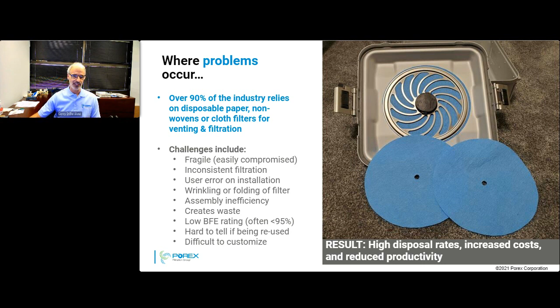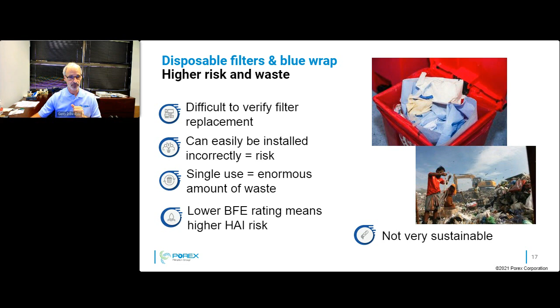Okay, so disposing of filters and blue wrap is, again, higher risk, higher waste. As I mentioned, it's very difficult to verify that the filter has been replaced. Even blue wrap sometimes can be reused, and that's, again, a very scary proposition. It can easily be installed incorrectly. There's no indicator to say that, hey, it's properly put in. They are single use, and that's how they're intended to be used, and certainly that generates a lot of waste. And then again, the lower the BFE rating, the bacterial filtration efficiency rating, means a higher healthcare-associated infection risk. So just remember those numbers go in opposite directions. The lower the BFE rating, the higher your hospital risk. So you want a super high BFE rating to ensure that your device, your container, is sterile and remains sterile during transit and use.